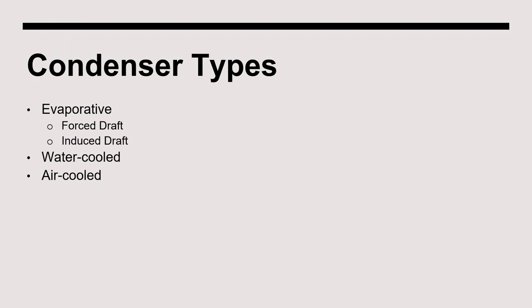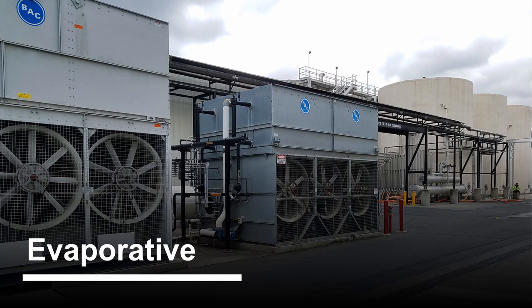There are several types of condensers used in ammonia refrigeration systems. These include evaporative, water-cooled, and air-cooled. The evaporative condenser type uses evaporative cooling to absorb heat from the ammonia inside the condenser. Evaporative cooling means that air and water are used in conjunction to achieve the lowest possible condenser temperatures. The interaction of the water and air causes a small portion of the water to evaporate, which cools the remaining water. The cooled water is what flows over the coil that contains ammonia inside the unit.